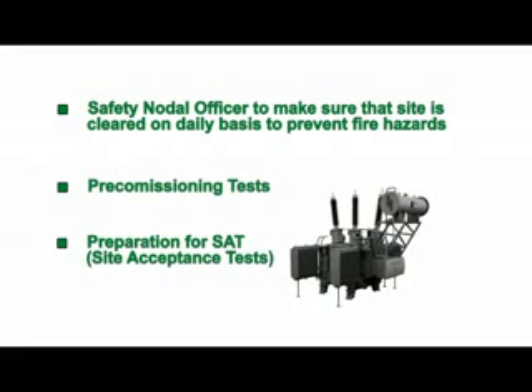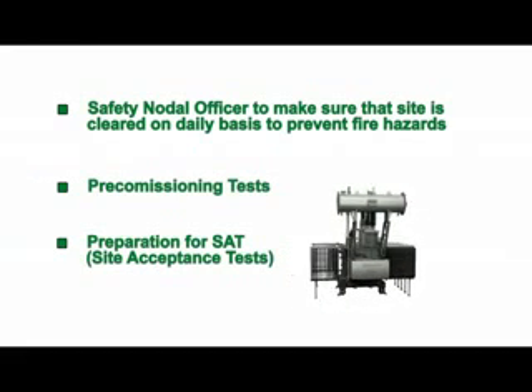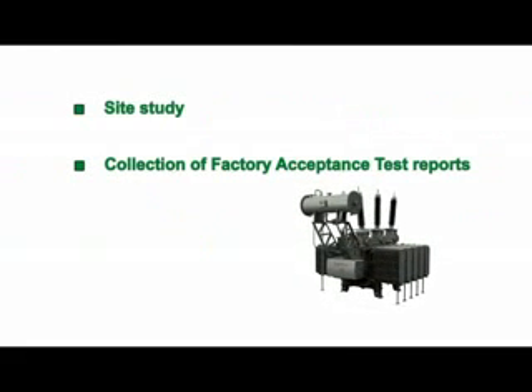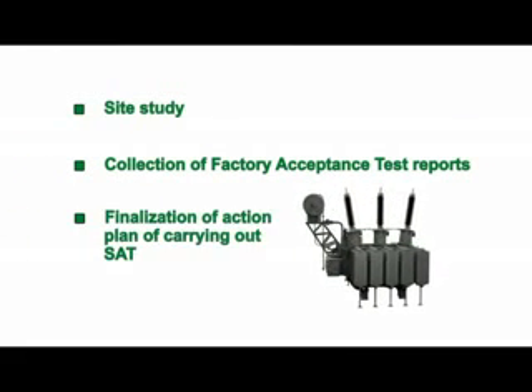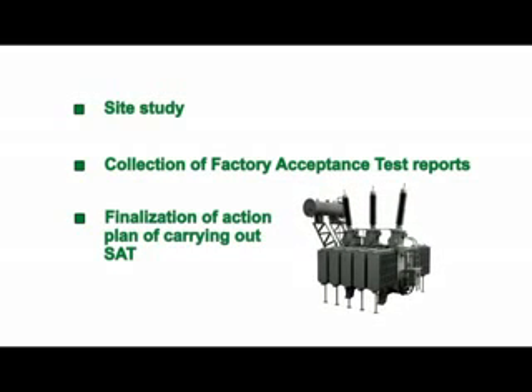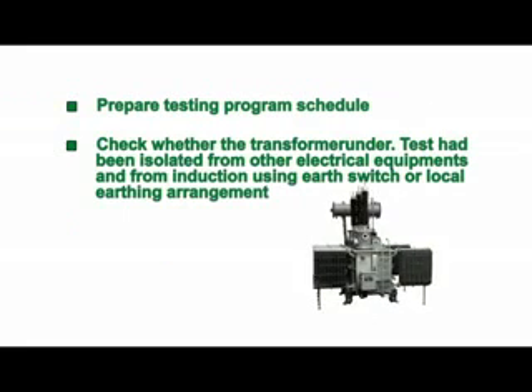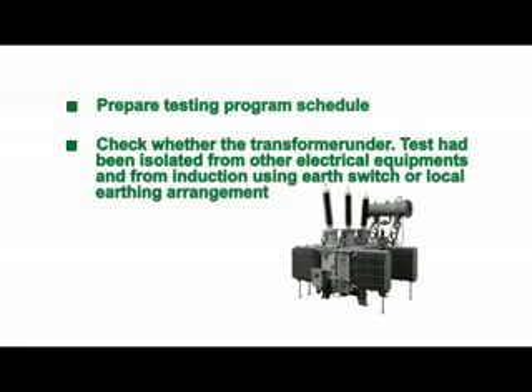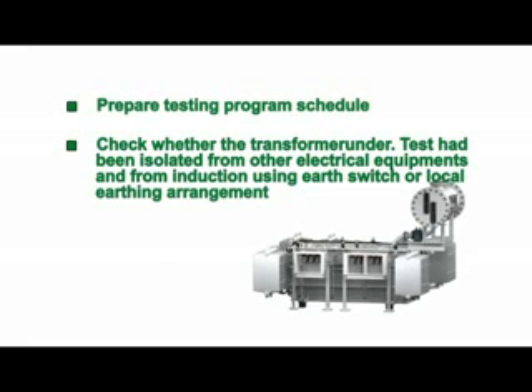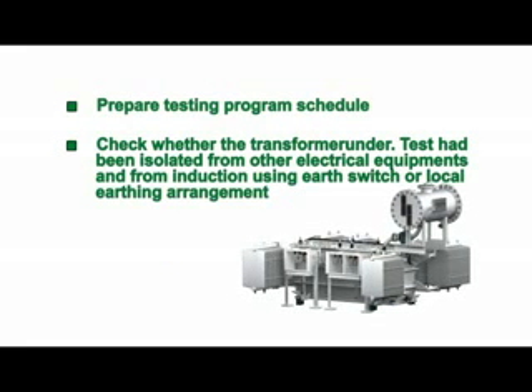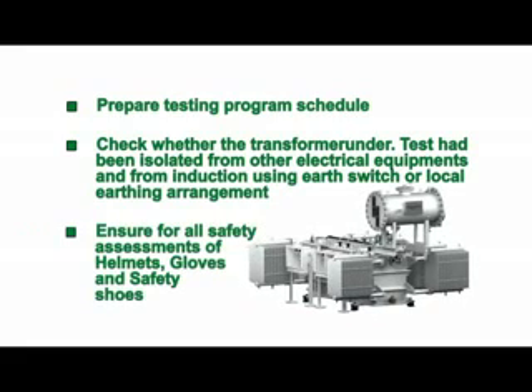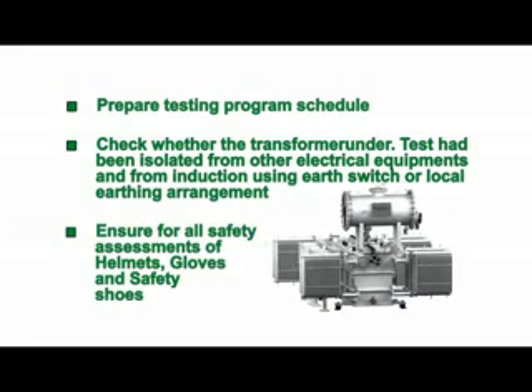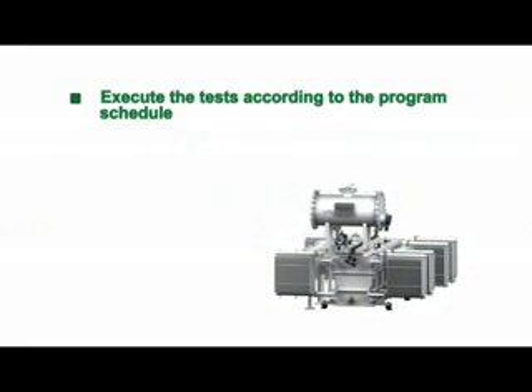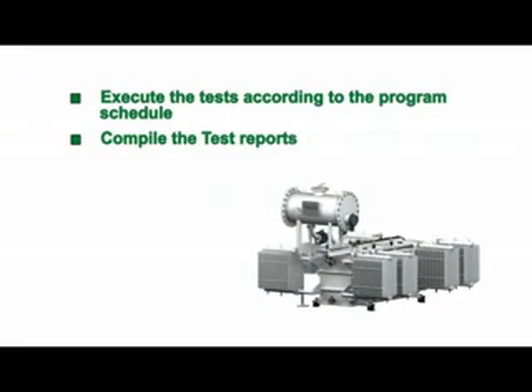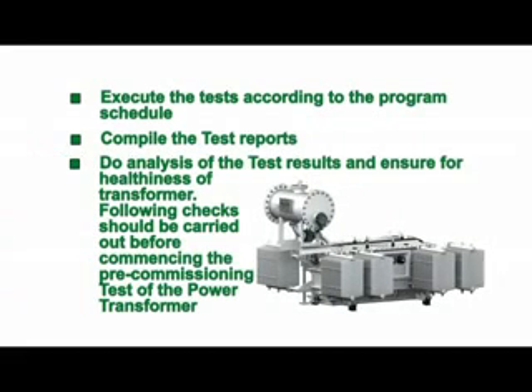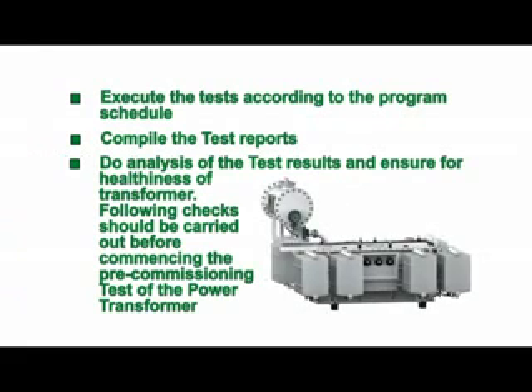Pre-commissioning tests. Preparation of SAT, Site Acceptance Test. Site study: collection of factory acceptance test reports. Finalization of action plan for carrying out SAT. Prepare testing program schedule. Check whether the transformer under test has been isolated from other electrical equipment and from induction, using an earth switch or local earthing arrangement. Ensure all safety assessments of helmets, gloves and safety shoes. Execute the test according to the program schedule. Compile the test reports. Do analysis of the test results and ensure healthiness of the transformers.